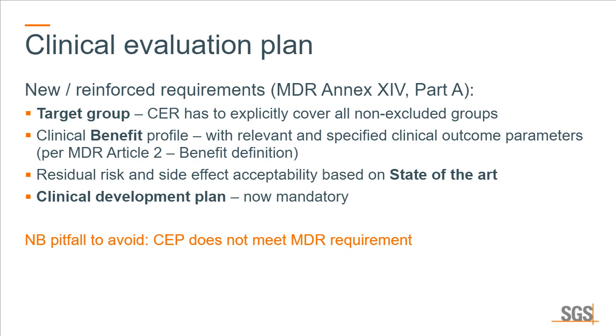And the typical pitfall that we encounter is that the clinical evaluation plan does not meet the MDR requirements. So the clinical evaluation plan, if it doesn't mention any of these concepts or just glosses over them or is too brief or is ambiguous in any of these aspects, it may be challenged by the notified body already.